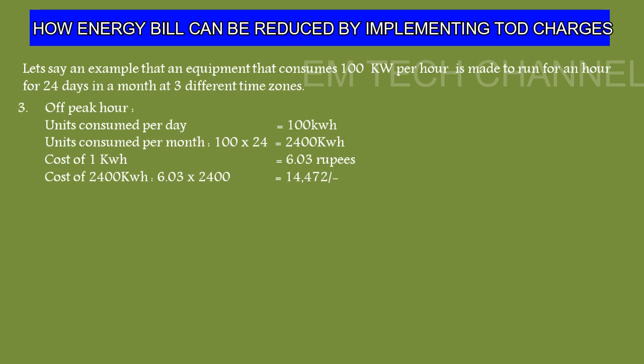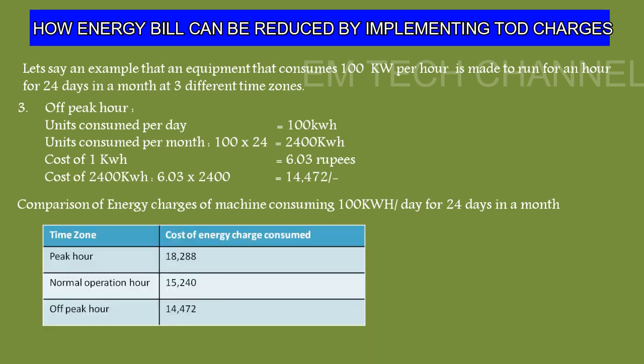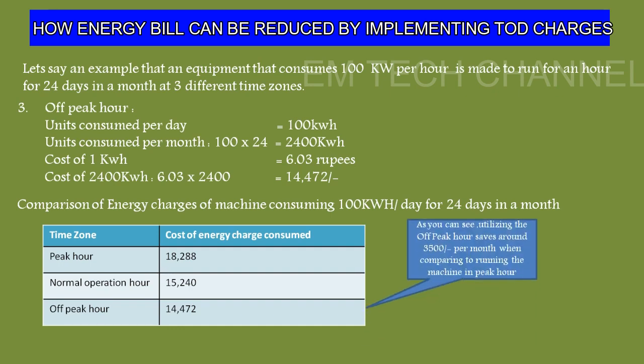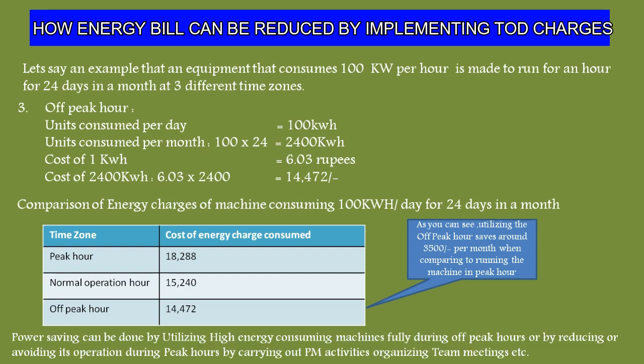Comparing the three categories: peak hour costs ₹18,288, normal operation costs ₹15,240, and off-peak hour costs ₹14,472. Running a machine in off-peak hours rather than peak hours saves around ₹3,500 per month without any investment. In practice, this may not always be possible due to customer demand and production volume, but the suggestion is to utilize high energy consumption machines as much as possible during off-peak hours and reduce their usage during peak hours by carrying out PM activities or organizing team meetings.